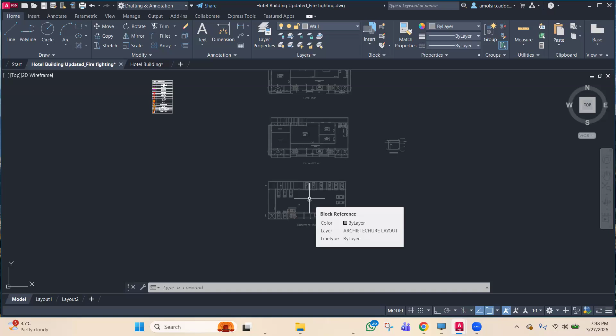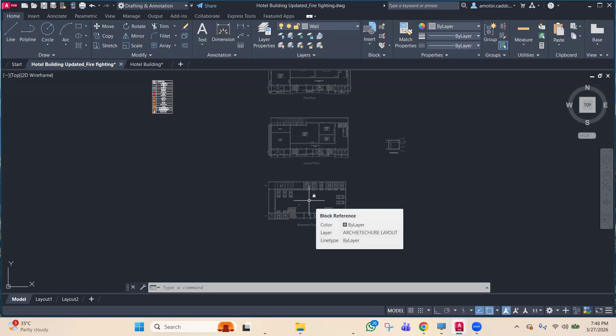So in case of light hazard, what is the sprinkler coverage, and what is the maximum and minimum distance we are taking? Maximum 15 feet, 4.5 meters, minimum 7.5 feet, correct? Yes, I'm saying it in feet, okay.